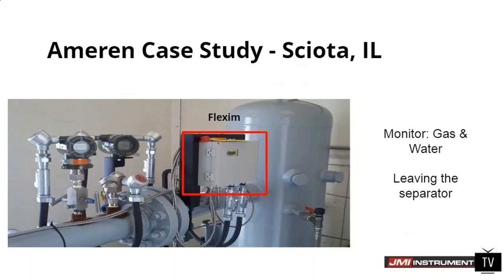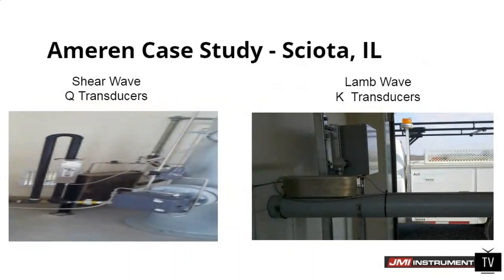Sorry, this picture is a little messed up. This shows the transducers mounted on a standpipe because it leaves the separator and the water goes through, I believe, an inch diameter pipe. We put a standpipe in here to keep this pipe full, and this is where we monitor the water leaving. Again, this is just a single channel standard volume flow. This is the transducer location right on the edge of the shanty. This is pretty common. We do this for several companies.